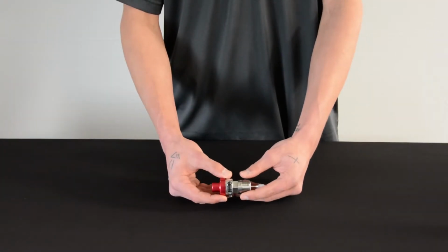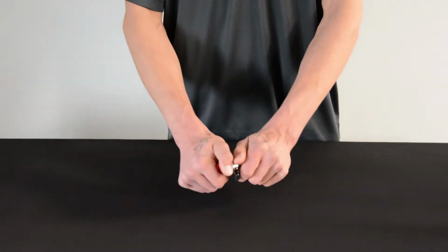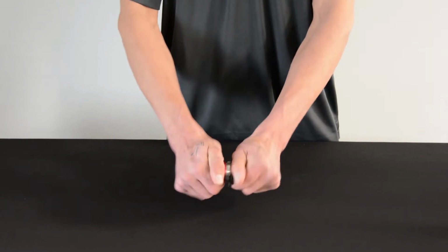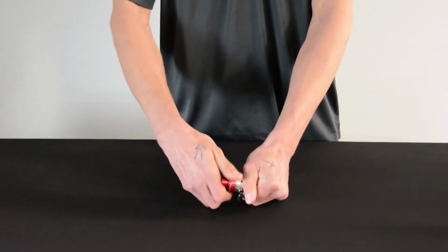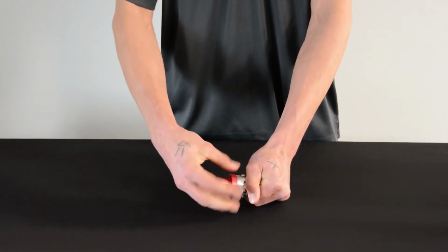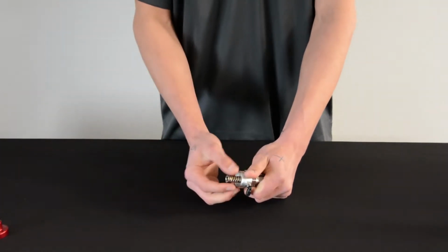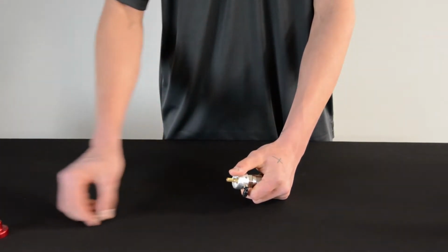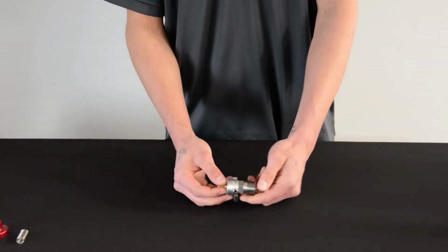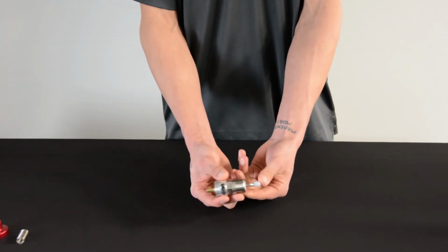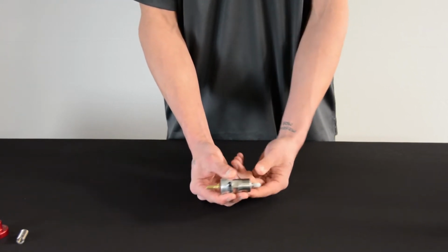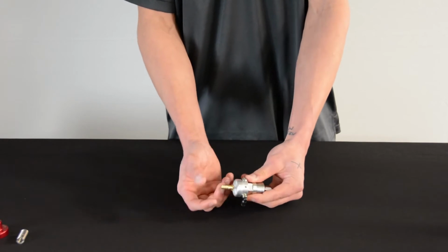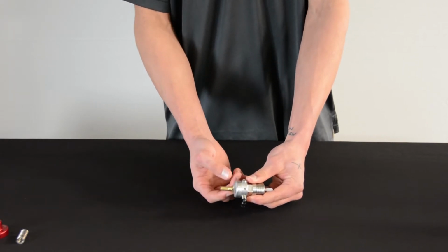We will start by disassembling the Poppet valve. You're going to remove the cap from the top of the Poppet valve, and you can put that off to the side. With that, your piston spring will come out, and you can put that off to the side. Then you're going to push your piston through the Poppet valve, exposing the locking nut indicator and the piston retaining nut.